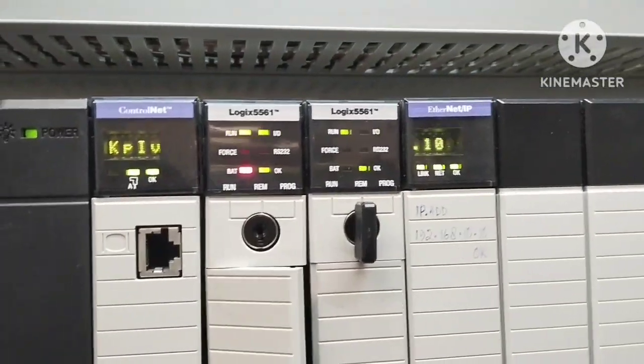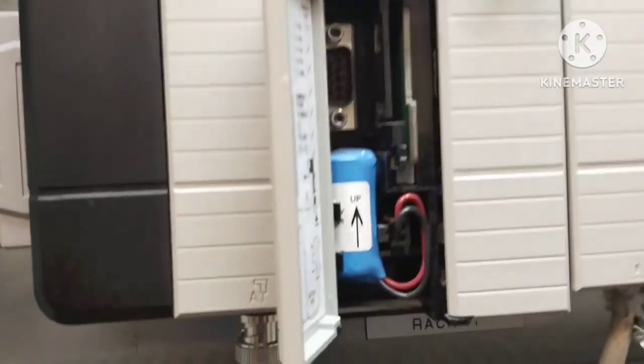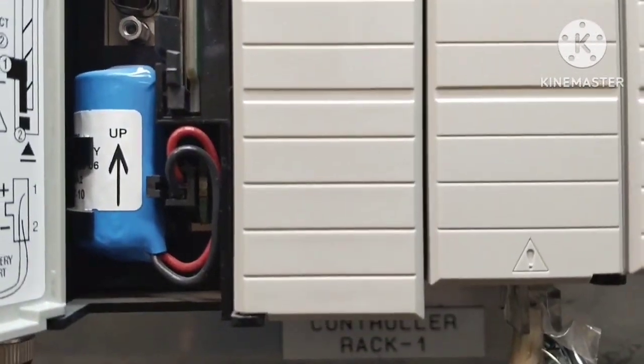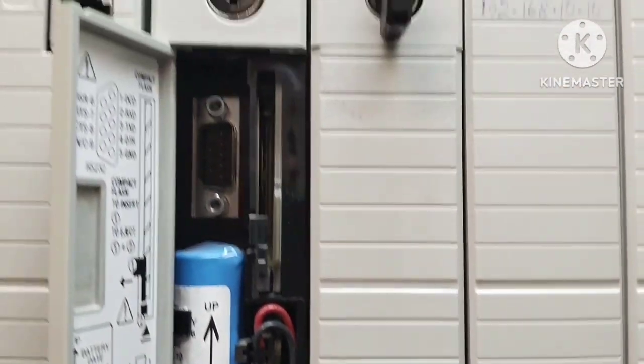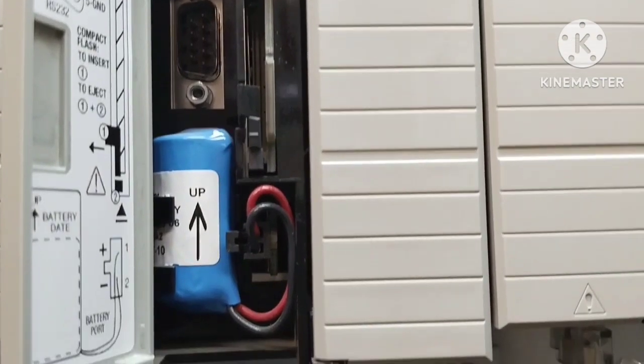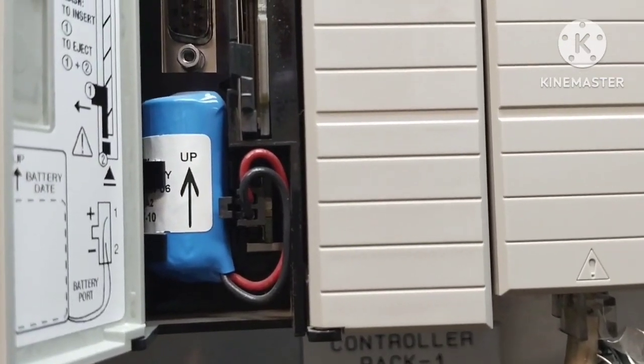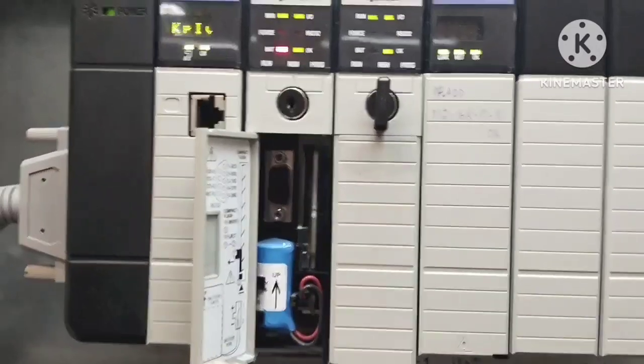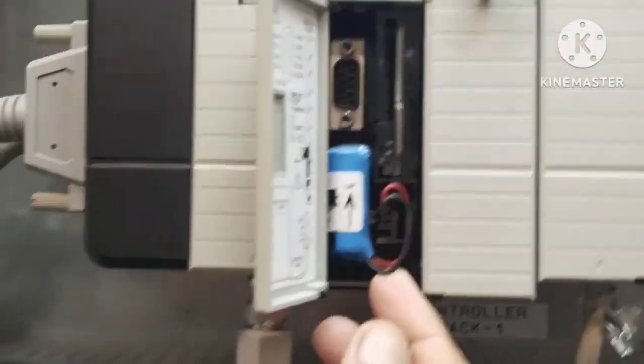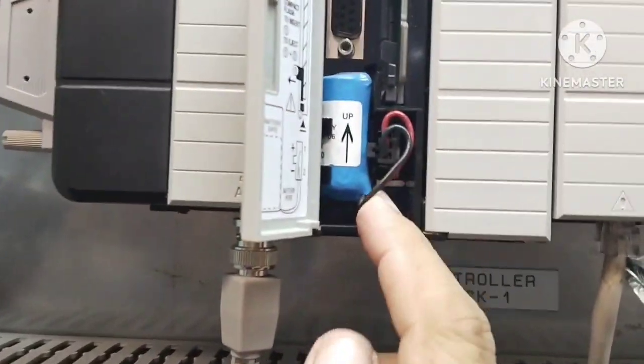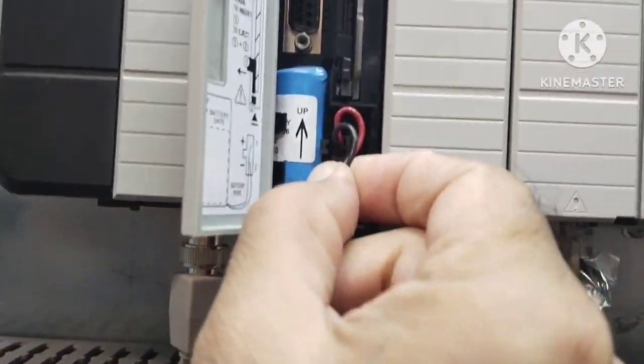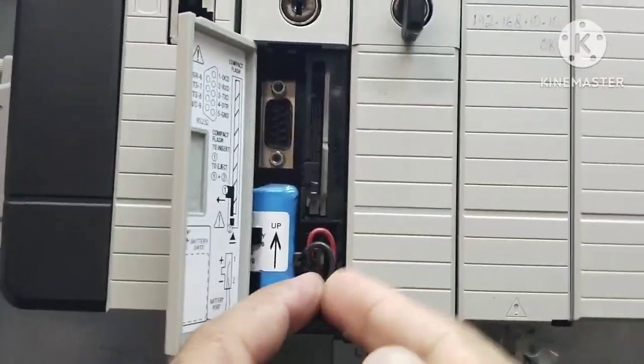First, open the front cover of the PLC carefully. You don't want to put too much force or move the PLC around while doing this. Locate the plug of the battery cell. Carefully remove it, and then take out the old battery cell from the PLC compartment.